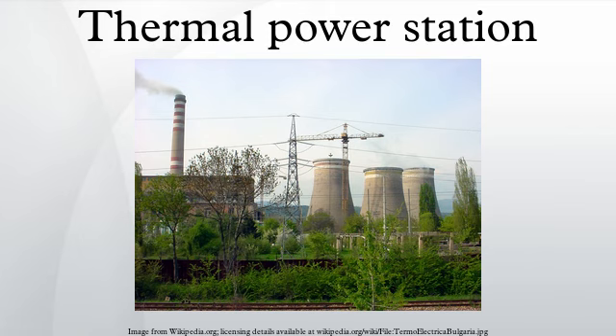The water enters the boiler through a section in the convection pass called the economizer. From the economizer it passes to the steam drum and from there it goes through downcomers to inlet headers at the bottom of the water walls. From these headers the water rises through the water walls of the furnace where some of it is turned into steam and the mixture of water and steam then re-enters the steam drum. This process may be driven purely by natural circulation or assisted by pumps.